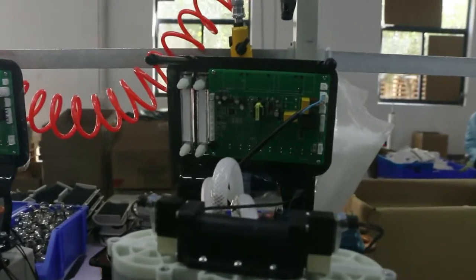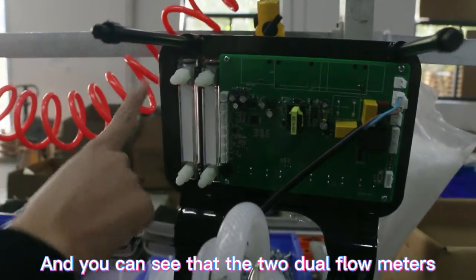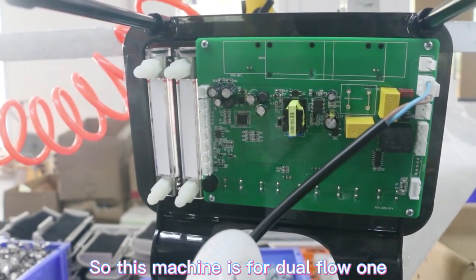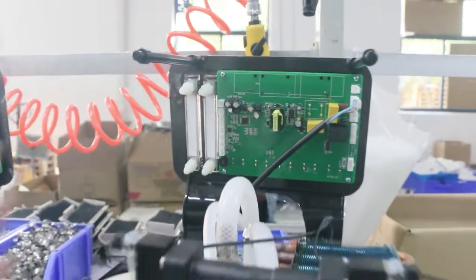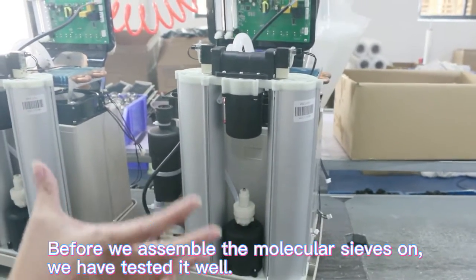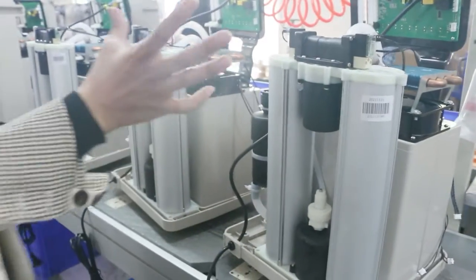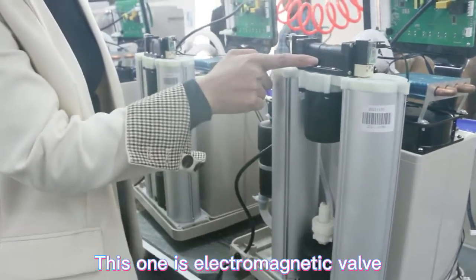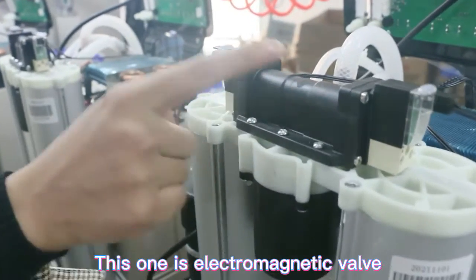Here you can see the PCB. There are two dual-flow outlets, so this is a dual-flow machine. We also need to install the molecular sieves. Before we assemble the molecular sieves, we have to test them first, and then we assemble them. This part here consists of the electromagnetic valves.